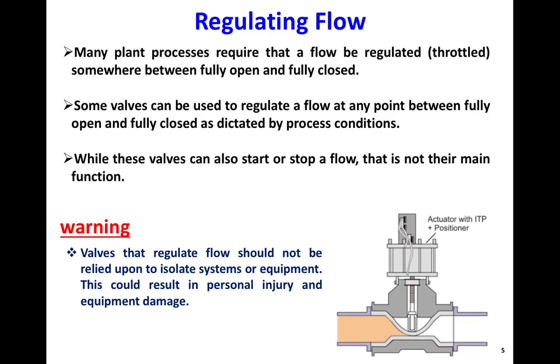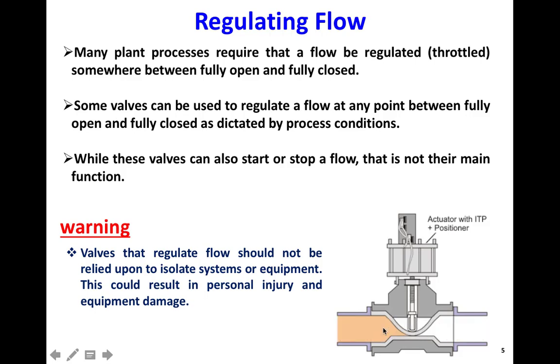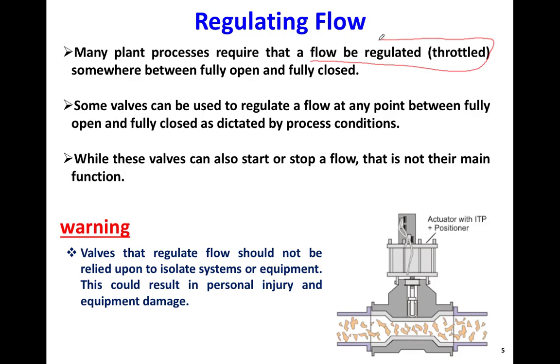A regulating valve is used to regulate the flow rate. By moving the diaphragm up and down, the flow inside the pipe can be adjusted — we can increase, decrease, or totally close the flow. Adjusting or regulating the flow rate is also called throttling the flow, which means regulating or adjusting the flow. Most of the time we need to adjust the flow rate between the two extreme cases, which are the fully open valve and the fully closed valve.